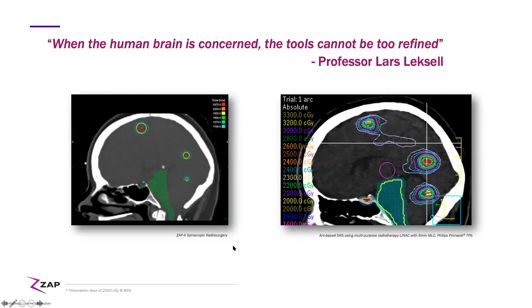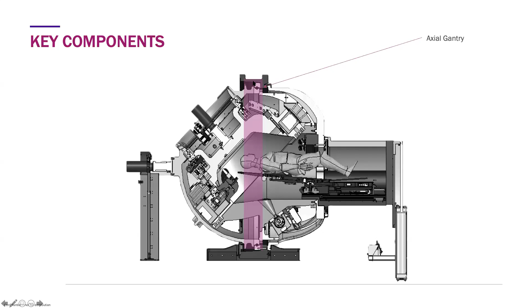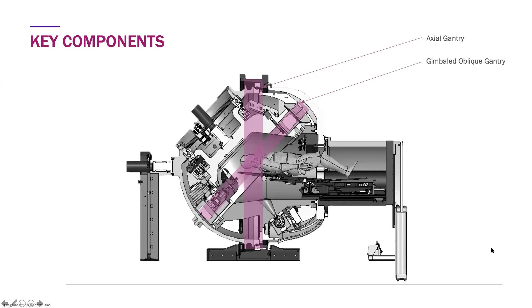This is how we achieve the dosimetry I've just defined. So there are two major rotational axes that define the device. We have this axial gantry, which is mounted to the floor. This is the stanchion that supports it, and it rotates around this axis, around the axial plane. Then we have an oblique axis. This is a big bearing in here that you really only see in cross-section, and this is the axis around which it rotates. These two axes intersect at a common isocenter, and that is where we get radiation crossfire. That is where we position the target of interest, and that's how we get the dosimetry I've just delineated.